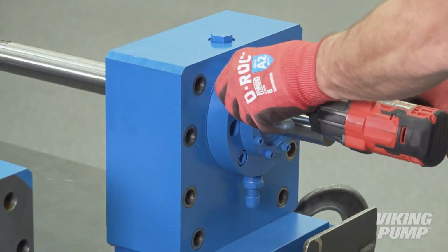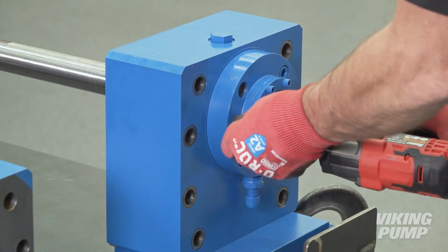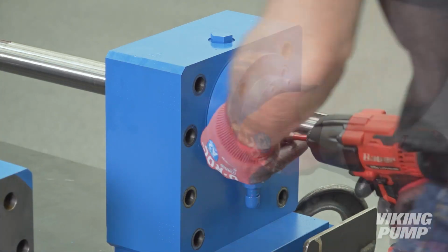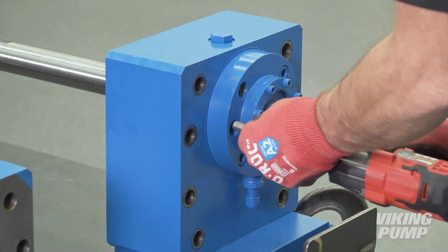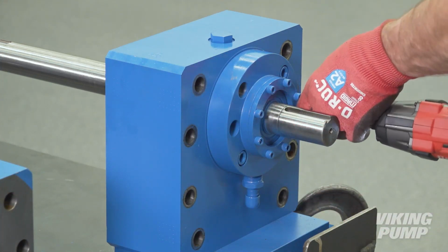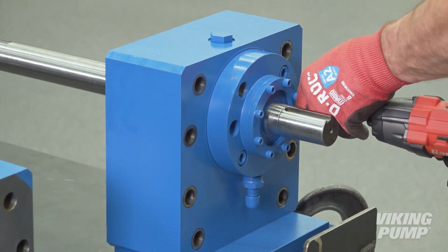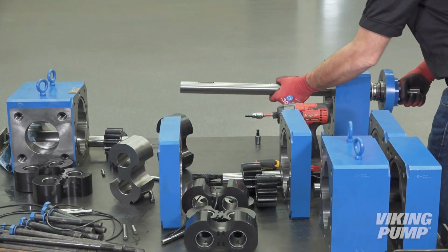For seal removal, loosen and remove the seal holder cap screws using a 3/8 inch Allen wrench. If necessary, use 2 of the cap screws as jack bolts to slowly press out the seal and shaft. Use the tapped holes at the 9 and 3 o'clock positions. You can now remove the seal and shaft.